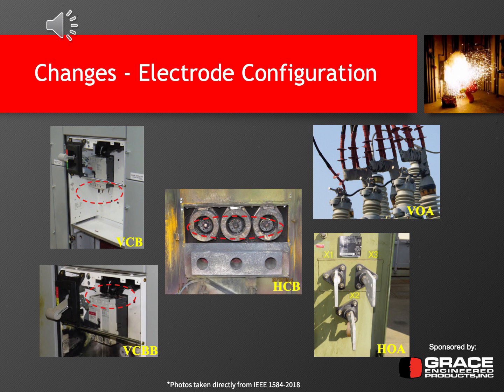And the upper right photograph is the VOA installation, which is the vertical open air. You can see these conductors are installed vertically, and they're not in an enclosure, so it's open air. And in the bottom right photograph, there is the HOA installation, which is horizontal open air. So these could be stabs or connection pads from a transformer, or some other device, like a circuit breaker potentially, that has the conductors pointing toward the individual standing next to it. And I just want to mention that each of these photographs was taken directly from the IEEE 1584 2018 edition, and they are included in the standard. So if you want to see some of the commentary on these photographs, please refer to that standard.